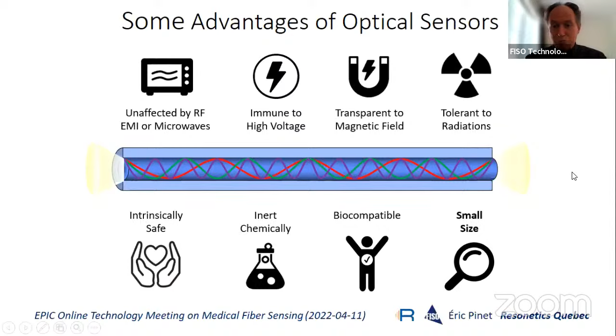They are fully transparent to magnetic fields, meaning they can be used under MRI. They're also tolerant to radiation, which matters for some therapies, and they are intrinsically safe—no electrical conduction, so there's no risk of electrocuting the patient. The optical fiber is fully chemically inert and biocompatible, and most importantly, the small size of the sensors is what really makes the difference compared to electrical sensors.